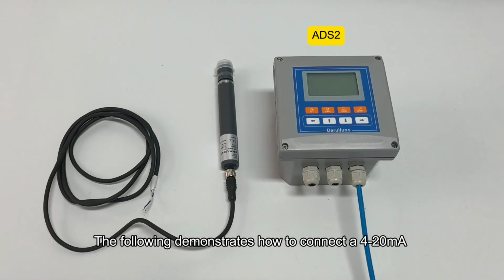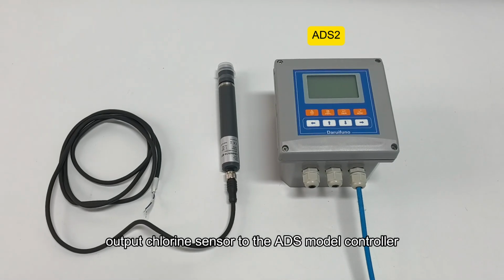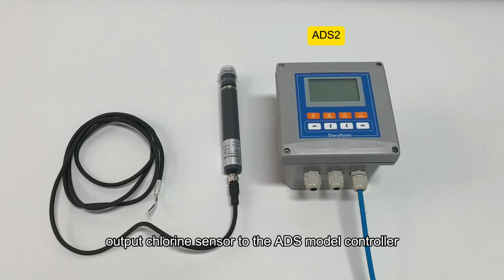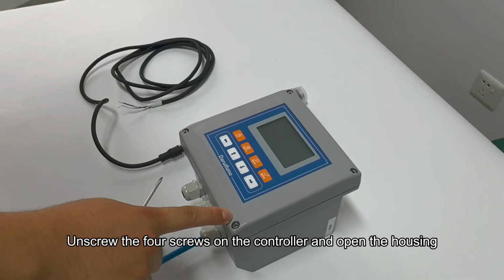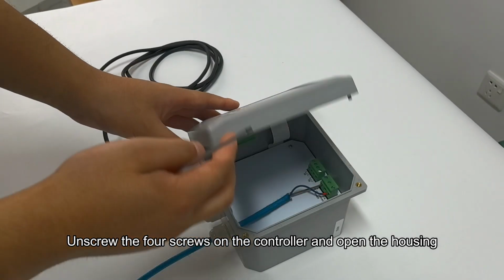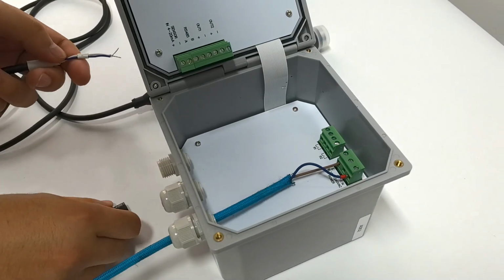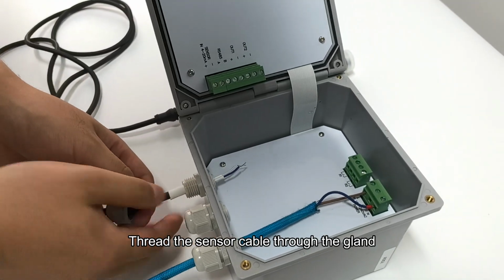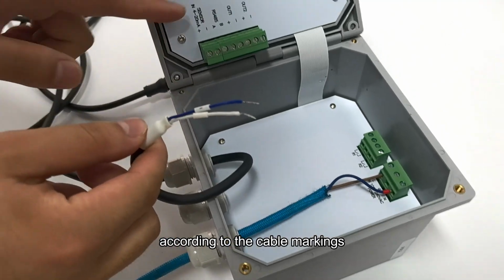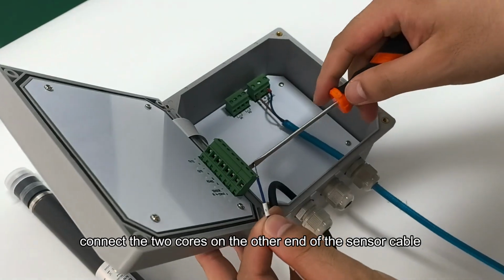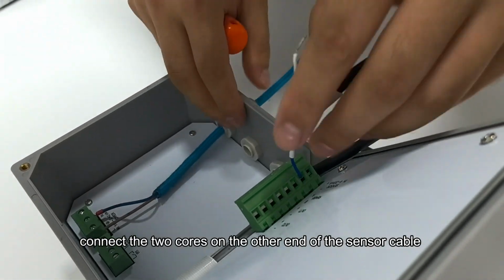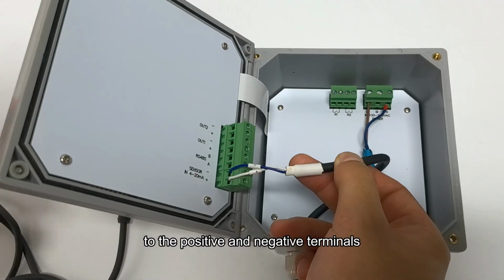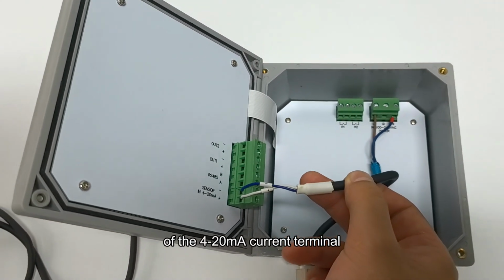The following demonstrates how to connect a 4 to 20 mA output chlorine sensor to the ADS model controller. Unscrew the 4 screws on the controller and open the housing. Thread the sensor cable through the gland. According to the cable markings, connect the 2 cores on the other end of the sensor cable to the positive and negative terminals of the 4 to 20 mA current terminal.